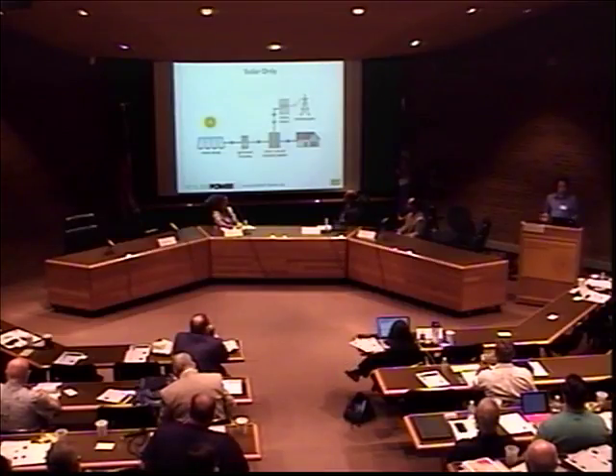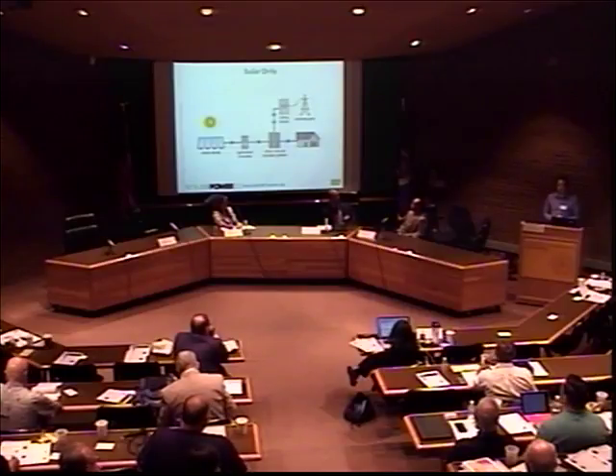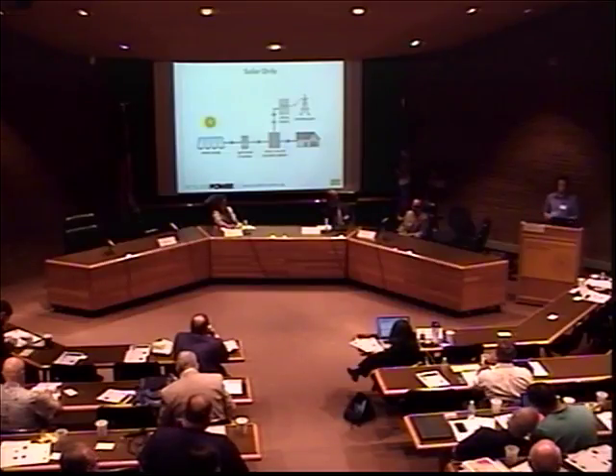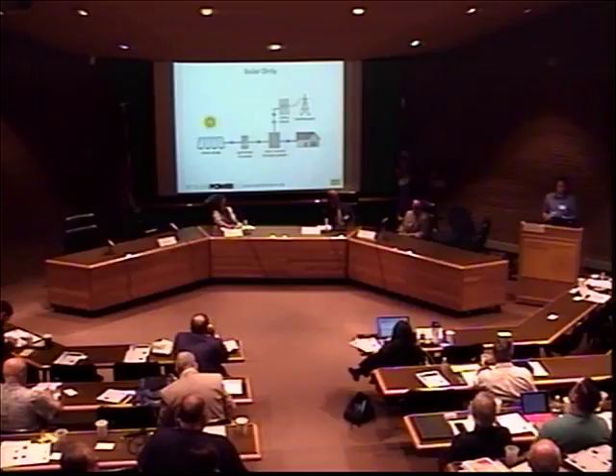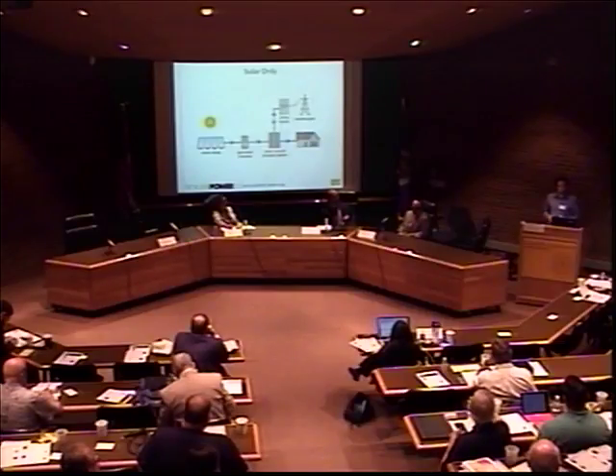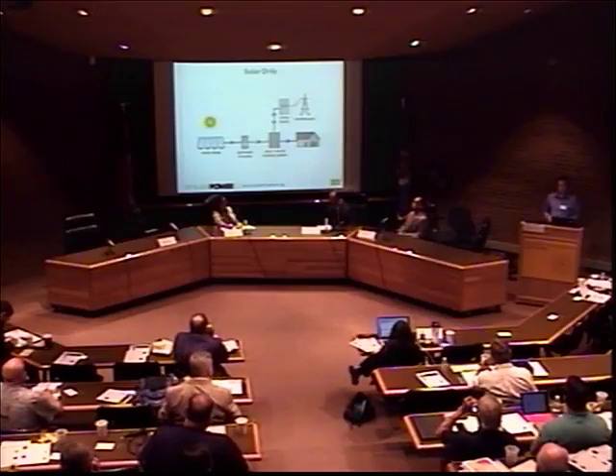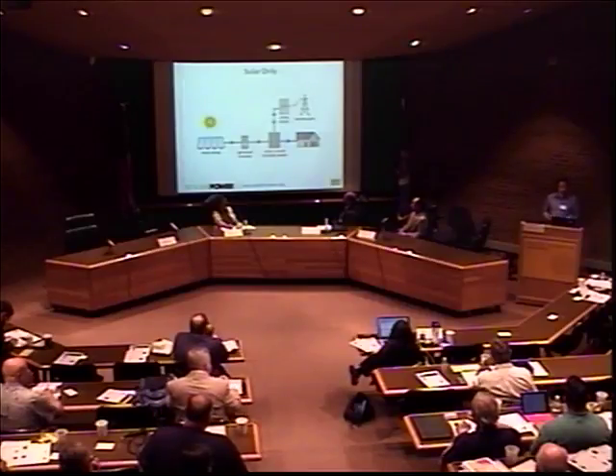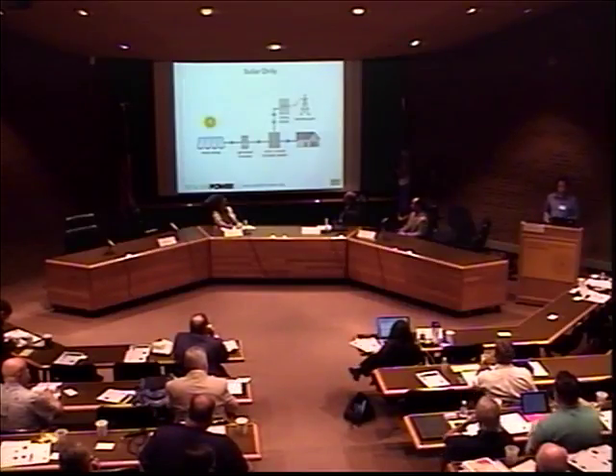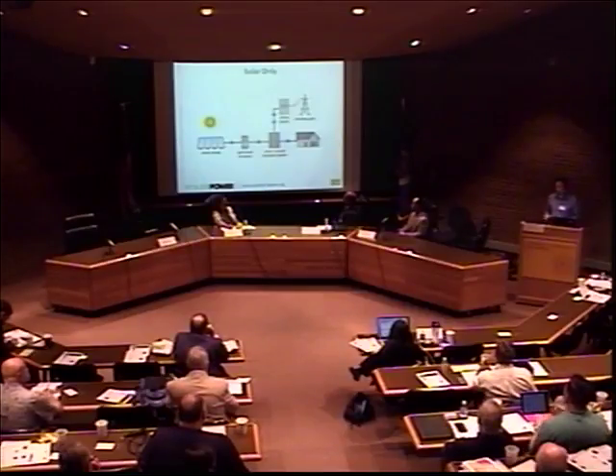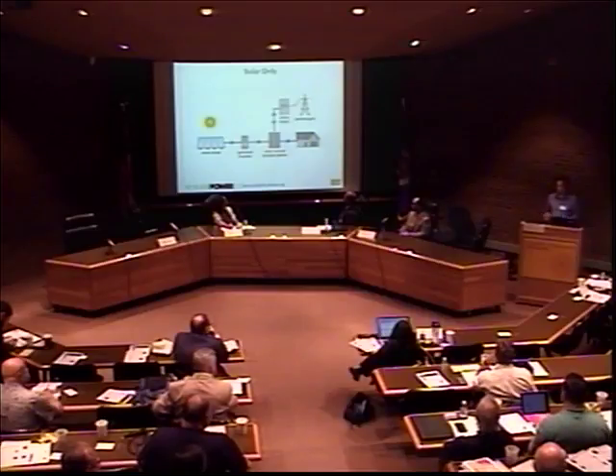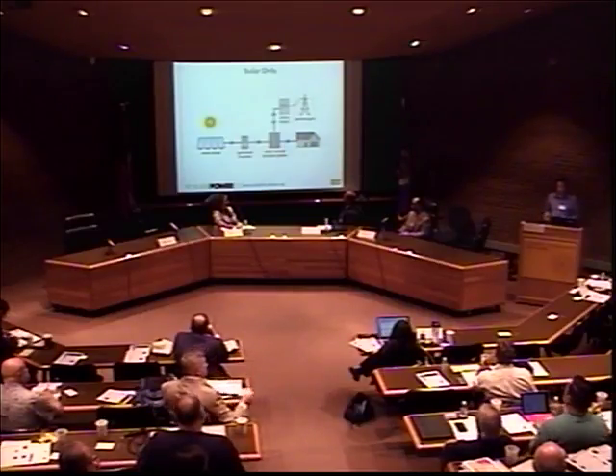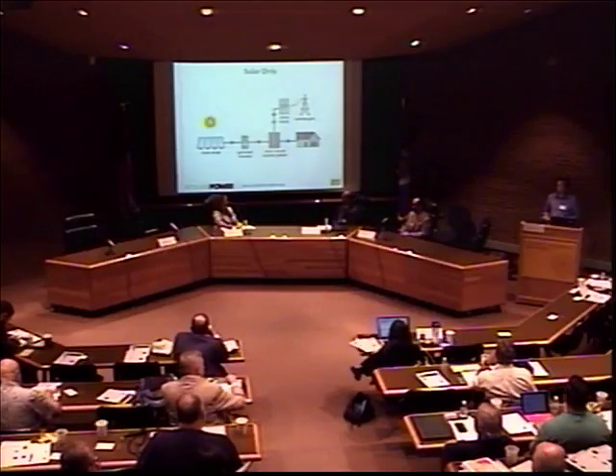I come from the Northeast, where a lot of resiliency action is taking place because of Hurricane Sandy. When Sandy hit, a lot of people with solar panels thought they'd be fine, but found their systems did not work because they're tied to the grid, and you can't have power fed back into the grid during outages since workers are out there trying to restore power and people might get hurt. So what you need is an inverter that can detach itself from the main grid and island itself during times when the main grid isn't there, insulating the system so it can become its own microgrid. Most solar systems out there do not have that kind of inverter. They are starting to be developed and are out there commercially now, but very few systems with solar have that kind of inverter.